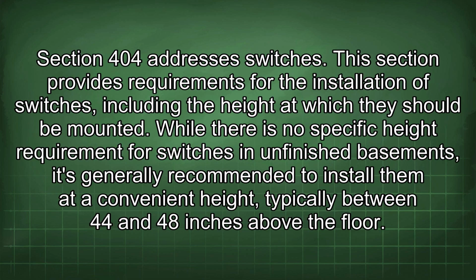Section 404 addresses switches. This section provides requirements for the installation of switches, including the height at which they should be mounted. While there is no specific height requirement for switches in unfinished basements, it's generally recommended to install them at a convenient height, typically between 44 and 48 inches above the floor.